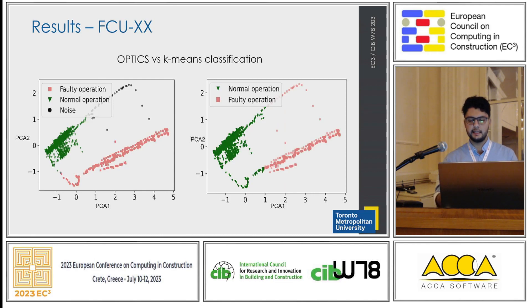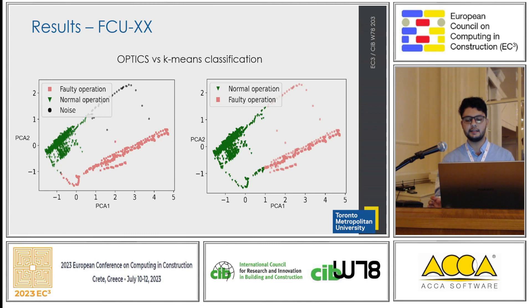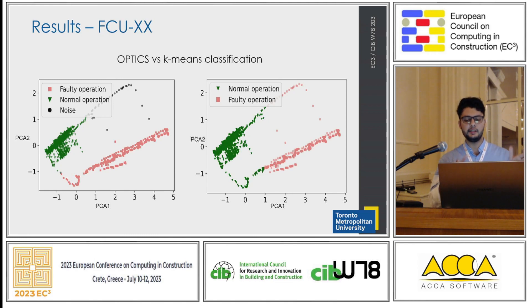This figure presents the results of OPTICS and k-means. There is a discrepancy between the results of OPTICS and k-means, which occurred due to OPTICS' ability to distinguish noise, while k-means falsely identified these as faults. We checked the results with a certified energy manager, and she verified that this indicates a lack of adequate chilled water flow to meet the cooling requirements, which was further validated by the time series data trace.